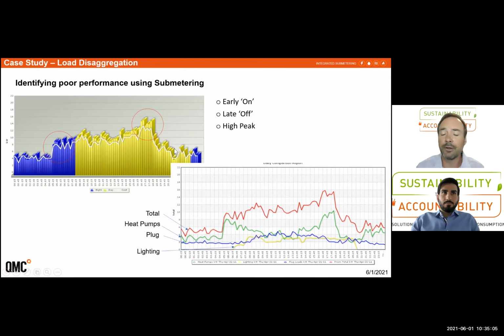This is another example of a building, a LEED project where we were metering. It's very typical for LEED projects to have a total consumption on an office tower floor and break that into lighting, plug load, and mechanical loads. And so we noticed a few floors were operating not within their expected range, as shown by this profile here. There were early starts and higher peaks near the end of the office day. And so we utilized the multiple meter points on that floor to do a bit of load disaggregation.